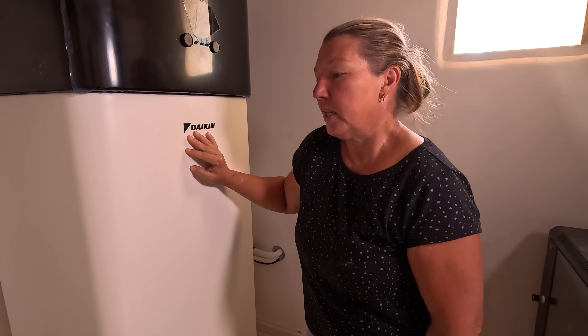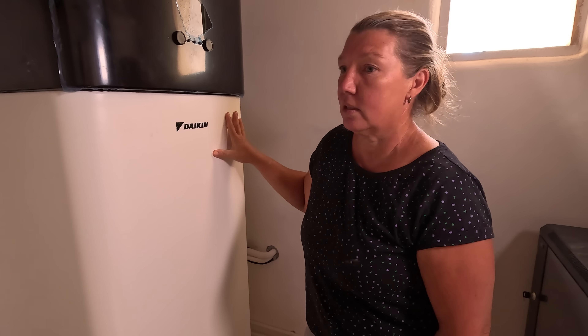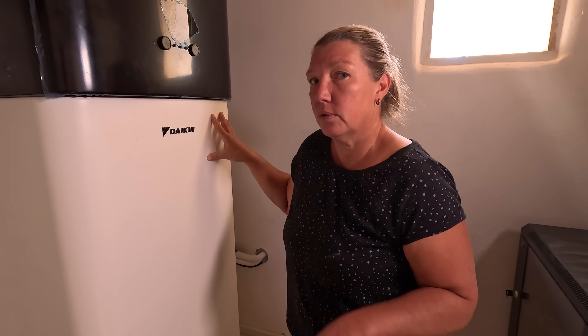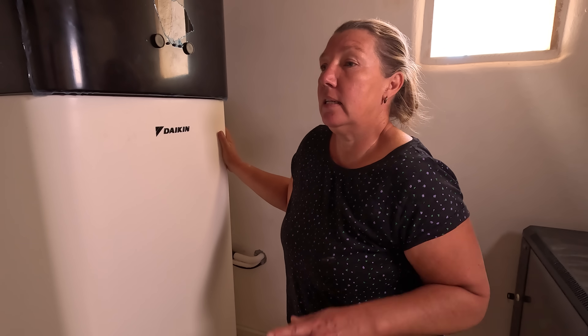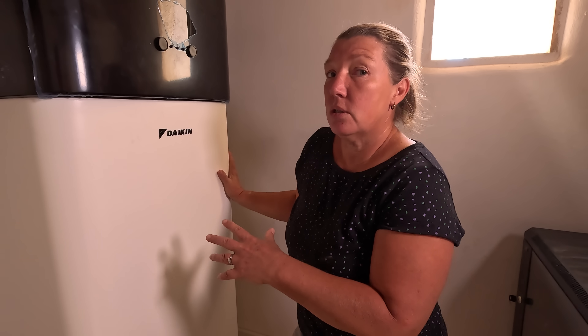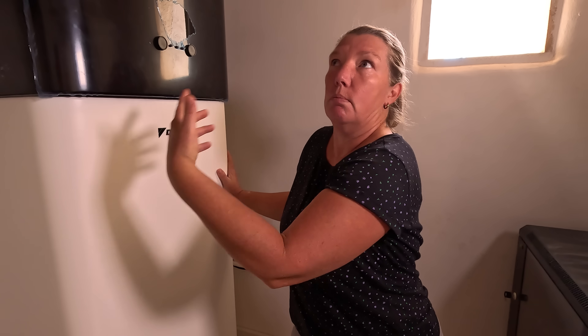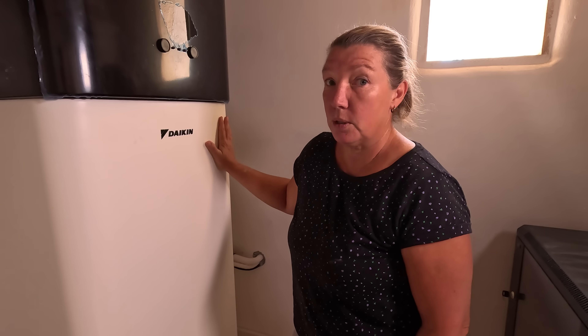Just like the outside unit runs a weekly defrost cycle if you're in a cold climate, so it does the defrost so it doesn't collect ice. This tank has no risk of Legionella because it has that cycle which runs when it needs to run. We will run this tank at a yet-to-be-determined temperature which will be optimal for our underfloor heating and the temperature at which we like to have showers. The guys who were here said it could be 45, it could be 48, it could be a little bit higher. We will work that out when we start using the hot water system, to optimize the temperature so that we're not adding too much cold water and using more energy than needed. It's likely to be around 50, but from a Legionella perspective this tank will look after that for us and we don't have to worry about it.